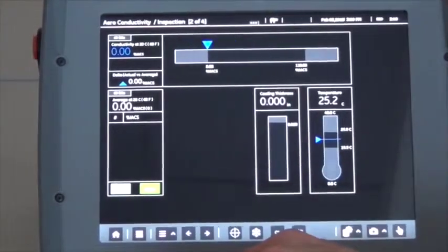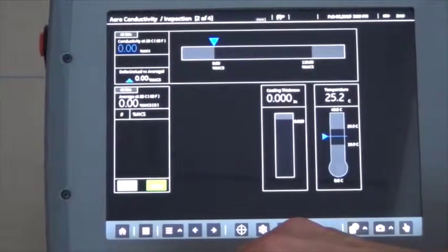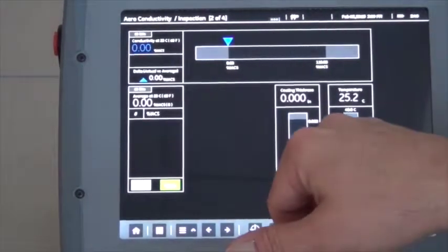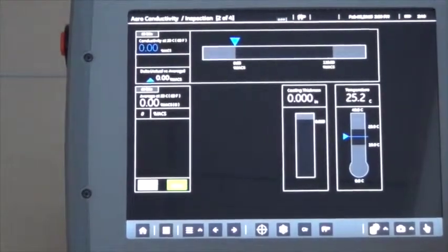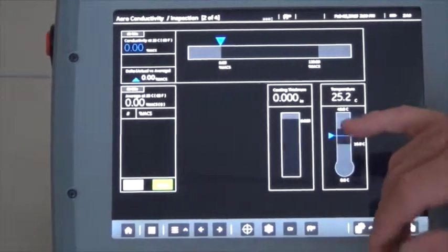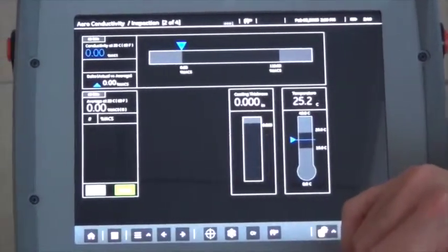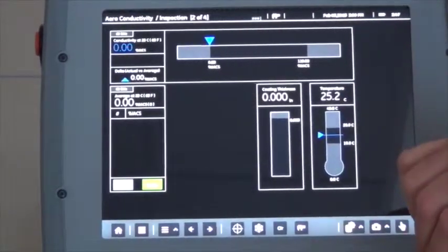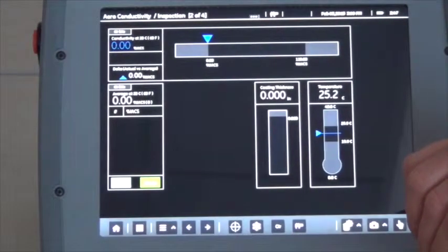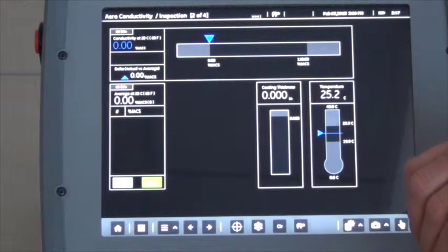In a similar vein, temperature has a large impact on conductivity. When we calibrate the instrument, the calibration temperature is recorded. We will show an alarm range of plus and minus 5 degrees Celsius from that calibration temperature, and we will compensate the conductivity readings anywhere from 0 degrees Celsius to above 40 degrees Celsius. If you get more than 5 to 10 degrees away from the calibration temperature, your accuracy may be impacted a bit, but it still gives quite acceptable results for most purposes.